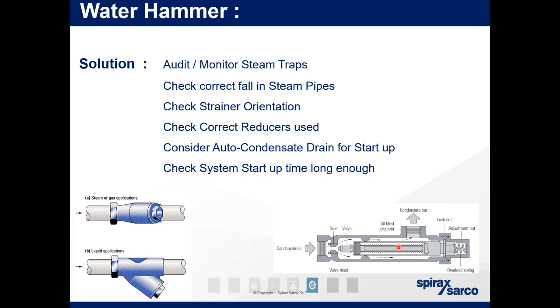So when it opens, there's suddenly a slug of water that passes down through it, just like opening an isolation valve. That can hit sensitive equipment, say like a filter. So it will rip through a filter, it will damage baskets and strainers. The faster it goes, the more energy it releases when it hits a surface. So the speed in relation to the energy is, effectively, you're giving more force for it to hit something.